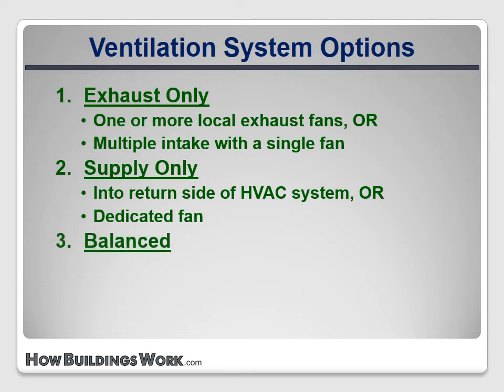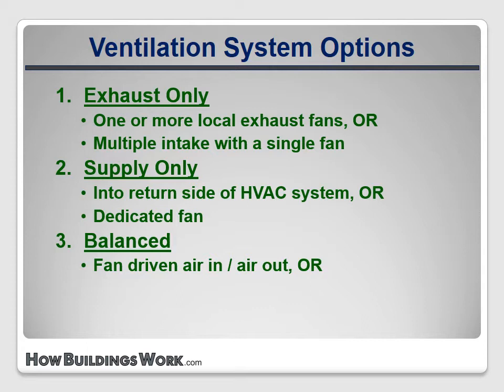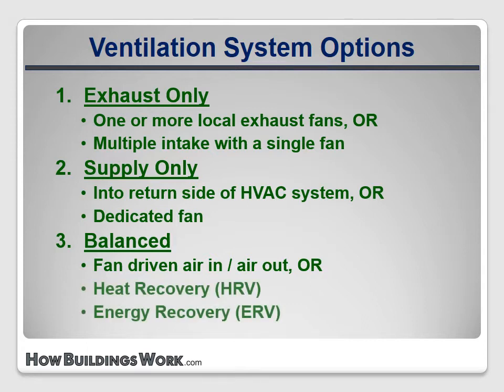Balanced systems use a balanced combination of supply and exhaust fans. The supply fans bring in the same amount of air that the exhaust fans pull out, so no pressures are created in the house by them. This can be done with separate fans, but when there are two air streams, it's possible to move heat and moisture from one stream to the other, improving energy use and comfort. We call these devices HRVs and ERVs — heat recovery ventilators and energy recovery ventilators.